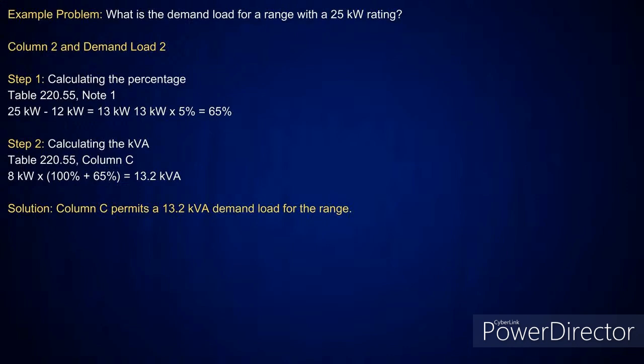Now, I'm going to be looking in column C because I'm over 12 kW. It's going to tell me I'm over 12 kW, so I'm going to look at the notes down here, okay? If I go look at note 1, it says over 12 kW through what? 27. And you can do this where they're all of the same rating, okay? When I get to where they're unequal ratings, then I'm going to look at note 2, all right? So what does it say? Let's just read what it says, and then I'll explain everything I'm doing here.